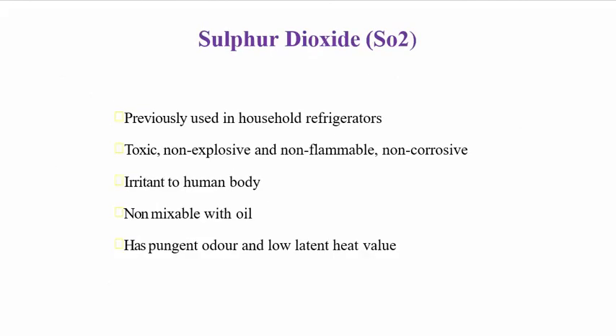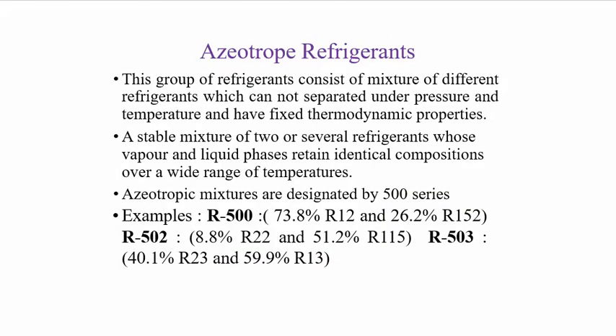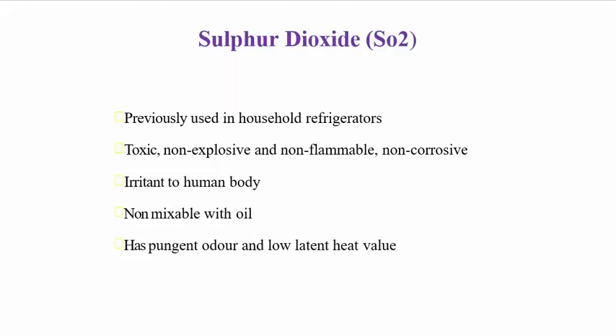Then we have sulphur dioxide. Sulphur dioxide was previously used in household refrigerators. It is toxic, non-explosive, non-flammable, and non-corrosive in nature, but it irritates the human body and does not mix with oil. It has a pungent smell and a low latent heat value.